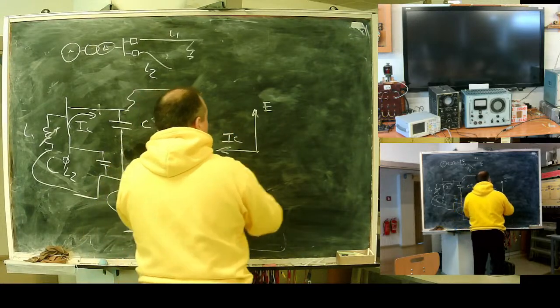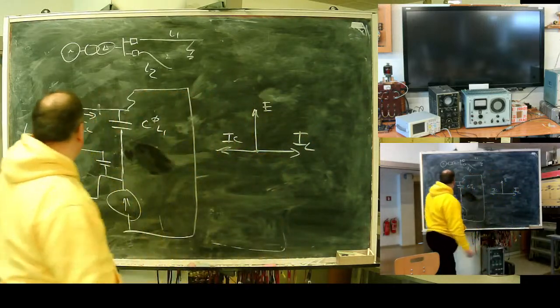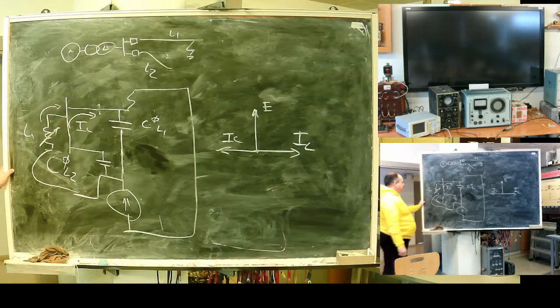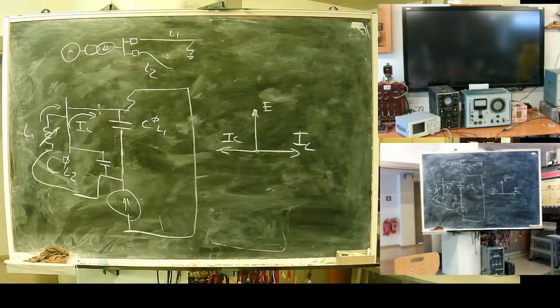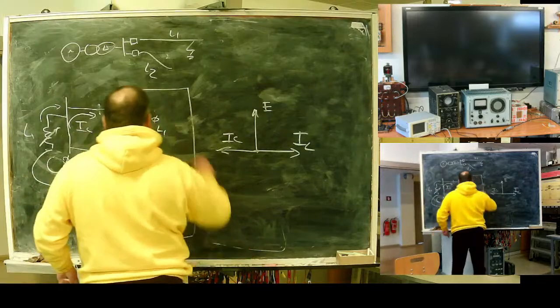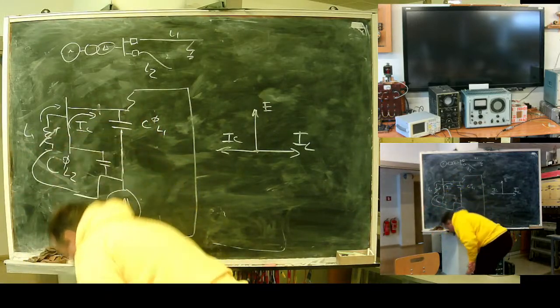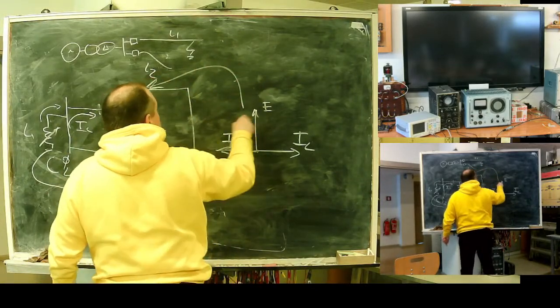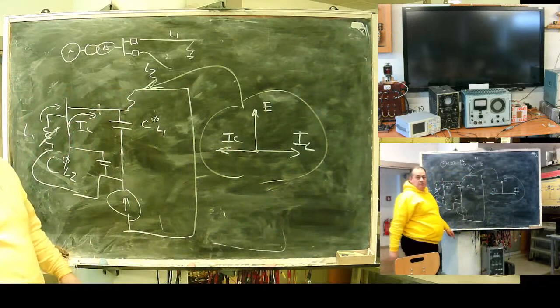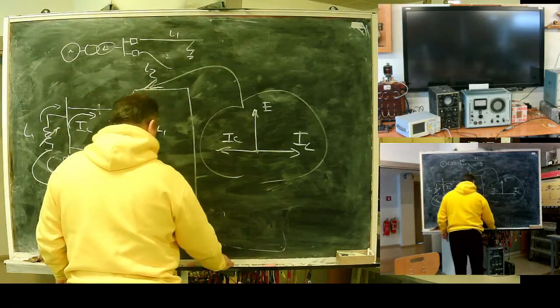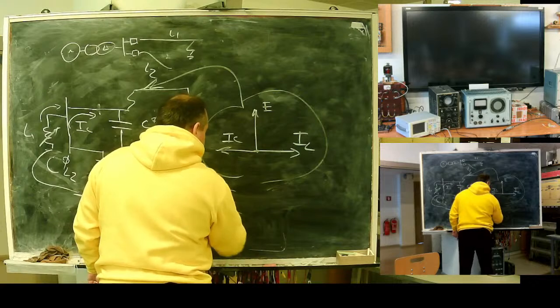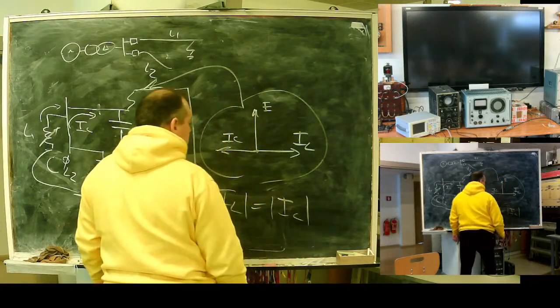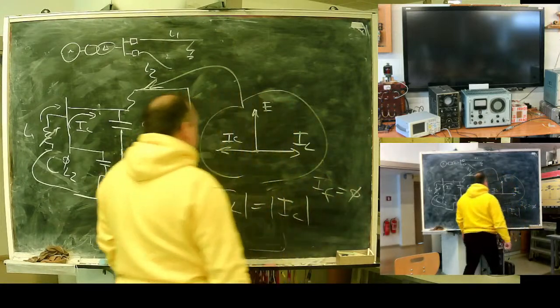Capacitive current in opposition, coil current through the coil. This adjustable coil called Petersen coil will produce one more current, current through coil. In the place of fault, this diagram, come back, is for place of fault. What you can achieve? You can fully compensate. In case of so-called resonant neutral, coil current will be equal to current of capacitor, meaning what? If fault is 0.